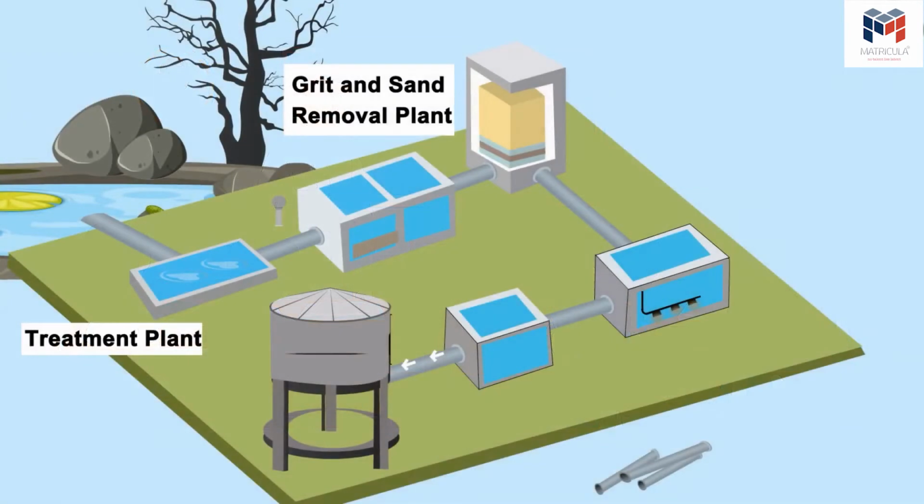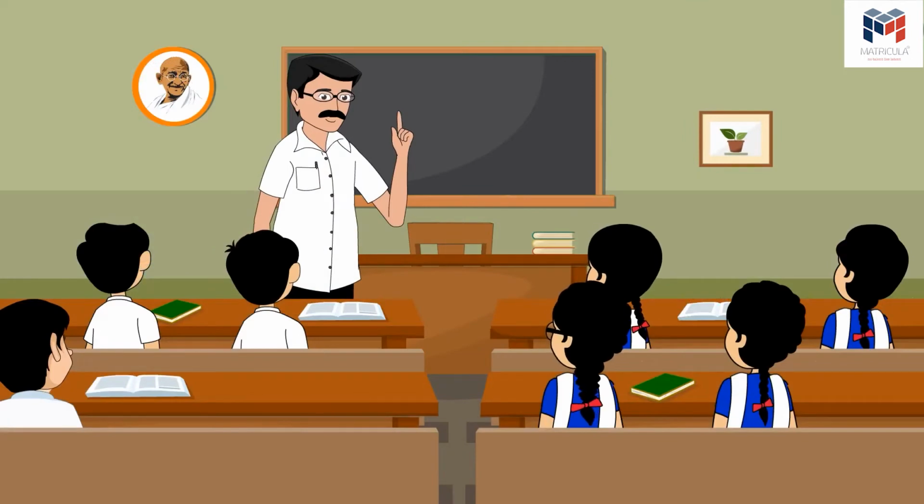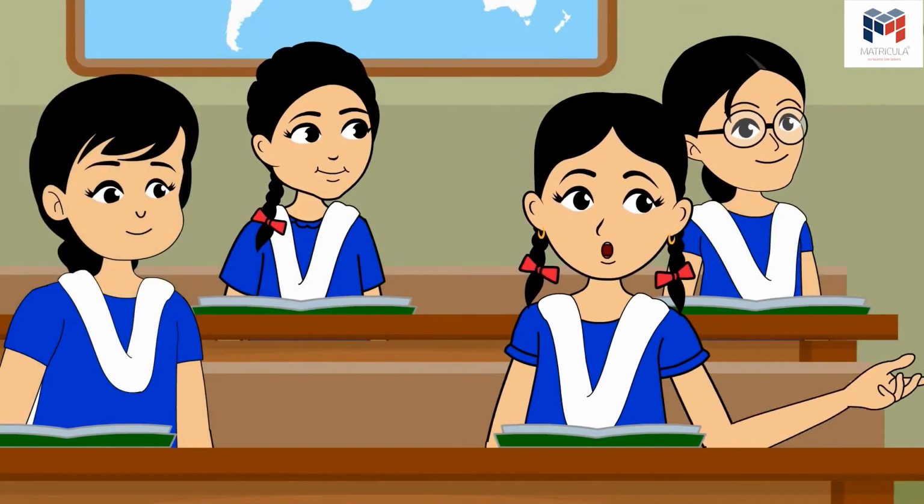After this, the contaminated water is kept in large tank for sedimentation. The contaminated water is left stagnant in a large tank about 5 meters deep. Heavy particles present in the contaminated water settle down, and relatively clean water at the top is taken for further treatment. The contaminated water in this tank is kept for at least 2 to 6 hours. Oil, fat, grease are extracted by the process of flotation. The primary step of treatment is over. The water is mostly clean with this step.